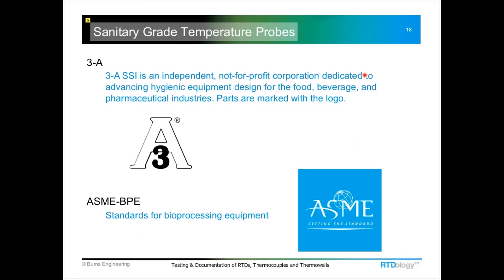Approvals or things that you may see with sanitary probes would be this 3A marking. The part will actually be labeled with this symbol, and this is a not-for-profit organization, and they actually audit manufacturers. I don't know if it's annually or every couple years, but they do show up and they do audit to make sure that you're producing the parts that meet their standards for hygienic equipment.